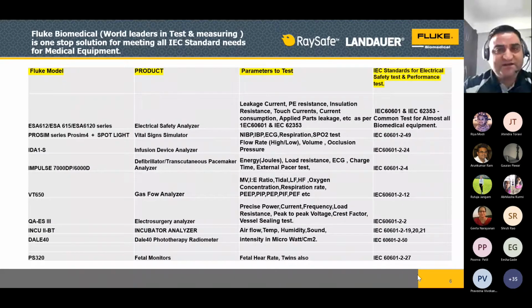I have made this slide in one. If you see, in one slide you will get all the information. If we are talking about the modality, the hospital equipment, we say device under test needs to be done. In the left column you will see our equipments, simulators and analyzers, which work as per the standards. Hospital equipments are the DUTs, device under test. Suppose you want to test a monitor. What will you do? The IEC standard says you have to do two tests: one is the electrical safety test and second is the performance test of the equipment.